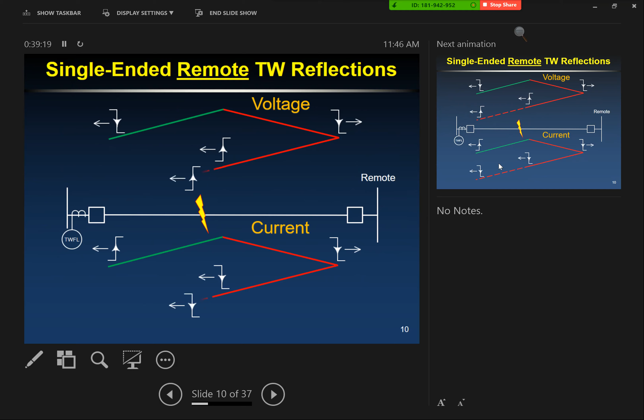...and it's a perfect short, we wouldn't get any energy passing through the fault. But if it has some impedance, which almost any fault I've seen, especially ground faults, has some impedance associated with it, plus if you consider the multi-phase coupling of the lines, your A, B, and C phases are all coupled with each other, and whatever happens on A phase shows up on B and C phase. Taking all that into account, you'll have some energy going through that fault, and so it passes through.